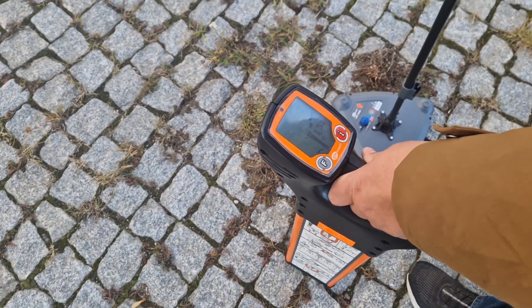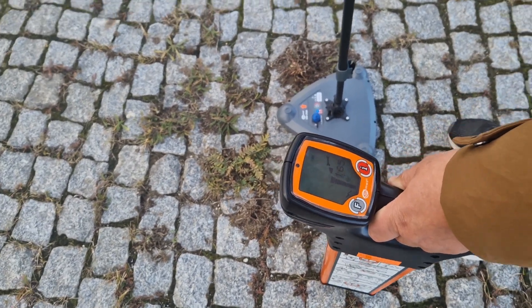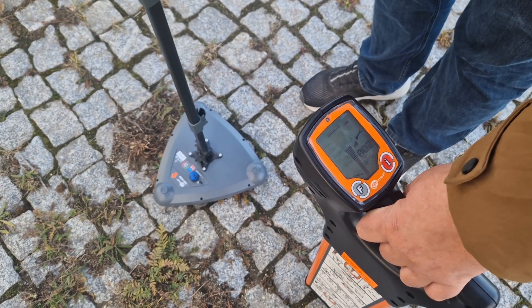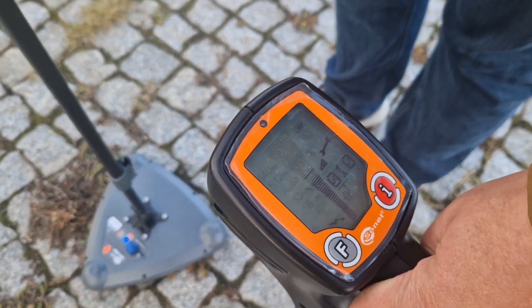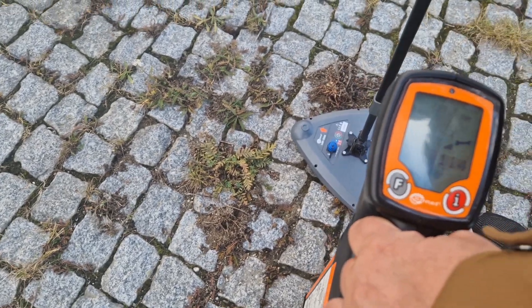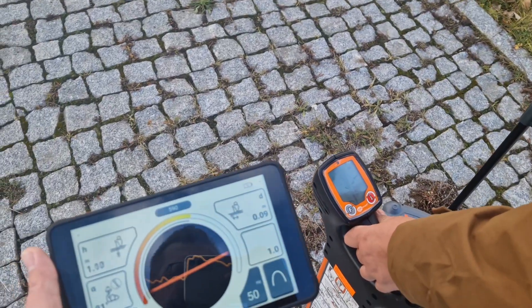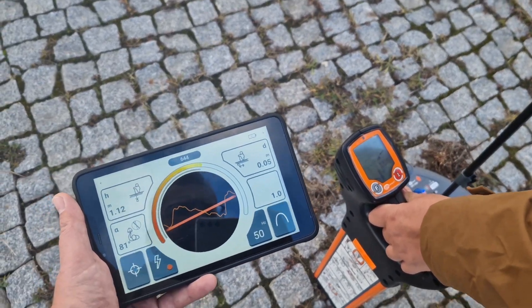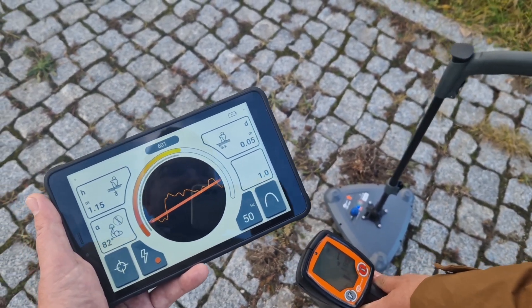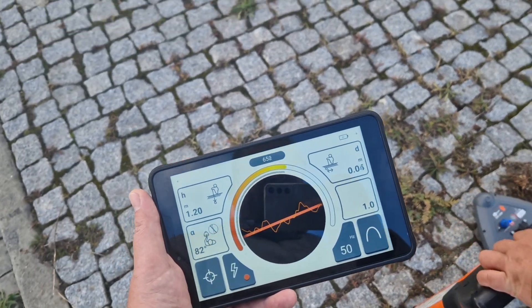In the case of the old design, that type of equipment has only one antenna inside. So when we turn the device, the readings become larger and then start decreasing — the readings are not stable. This can cause confusion when tracing a live cable. This is a huge improvement compared to the old type of underground cable locators with one antenna. Thanks to the three independent 3D antennas, we can trace the cable very stably and accurately.